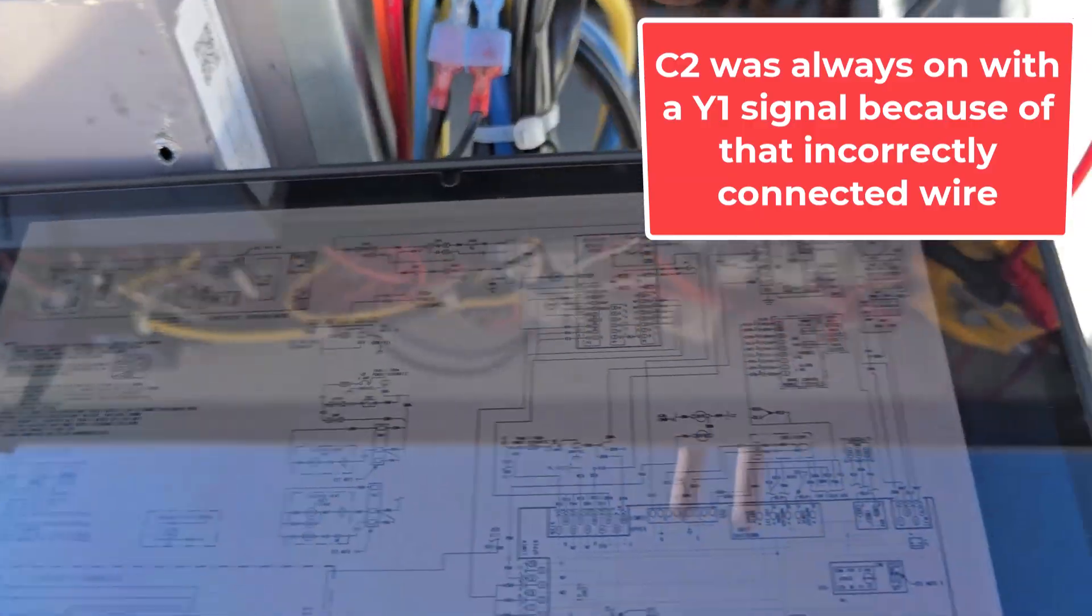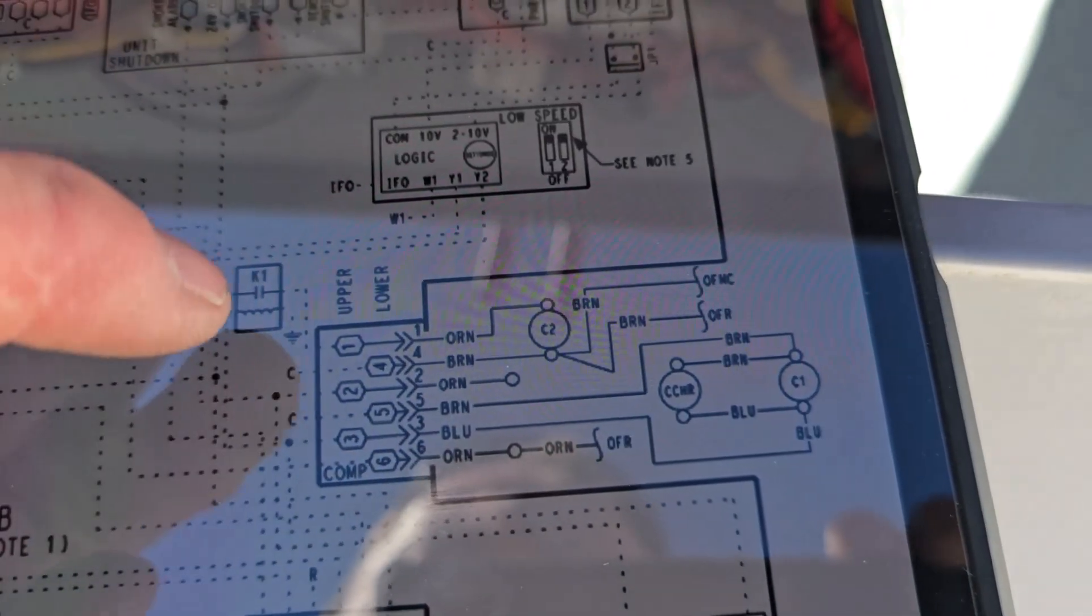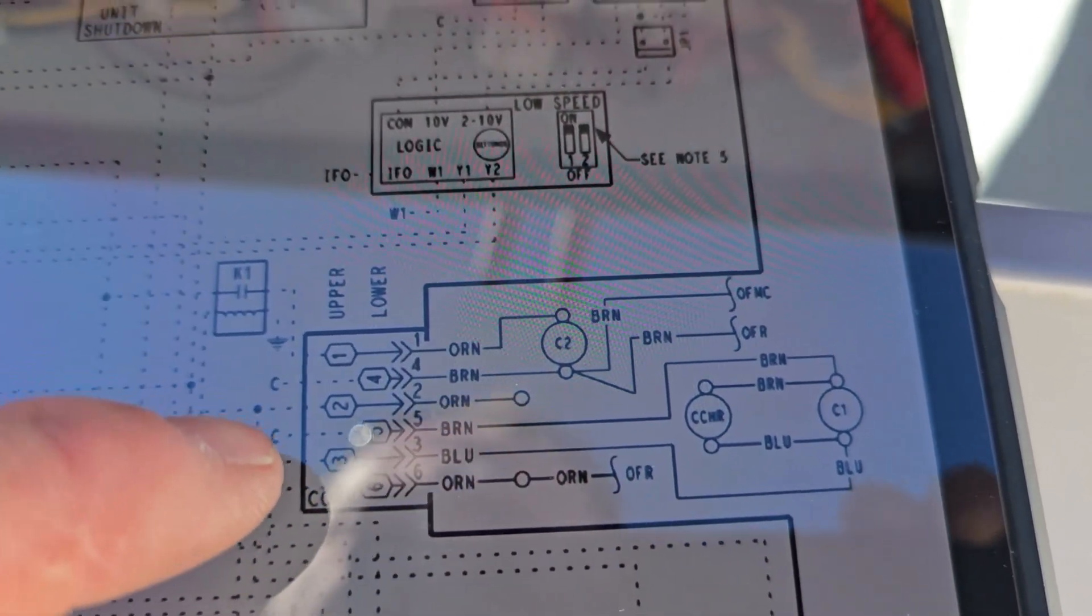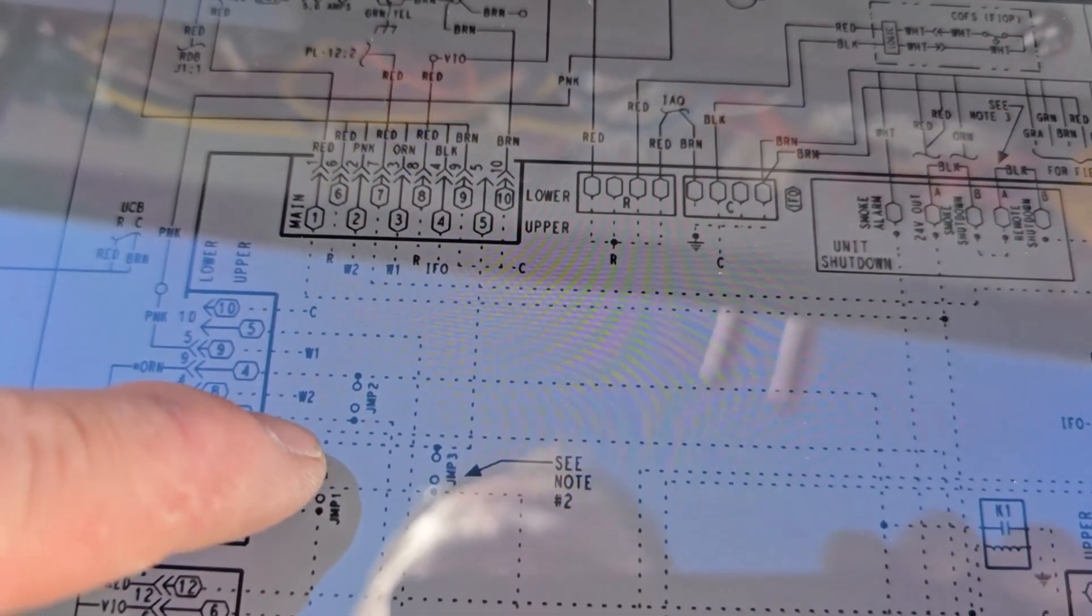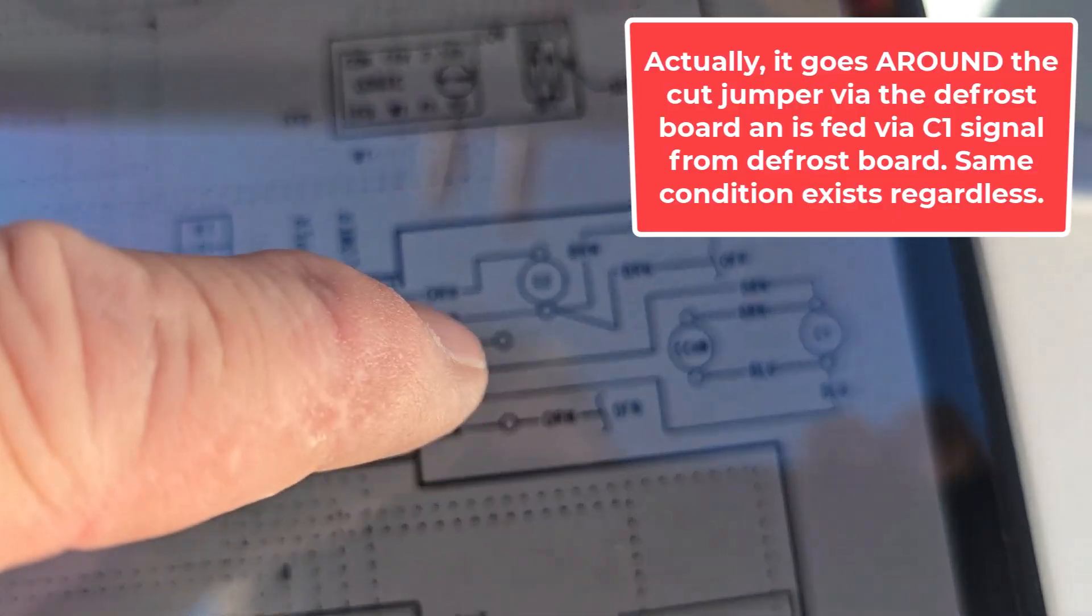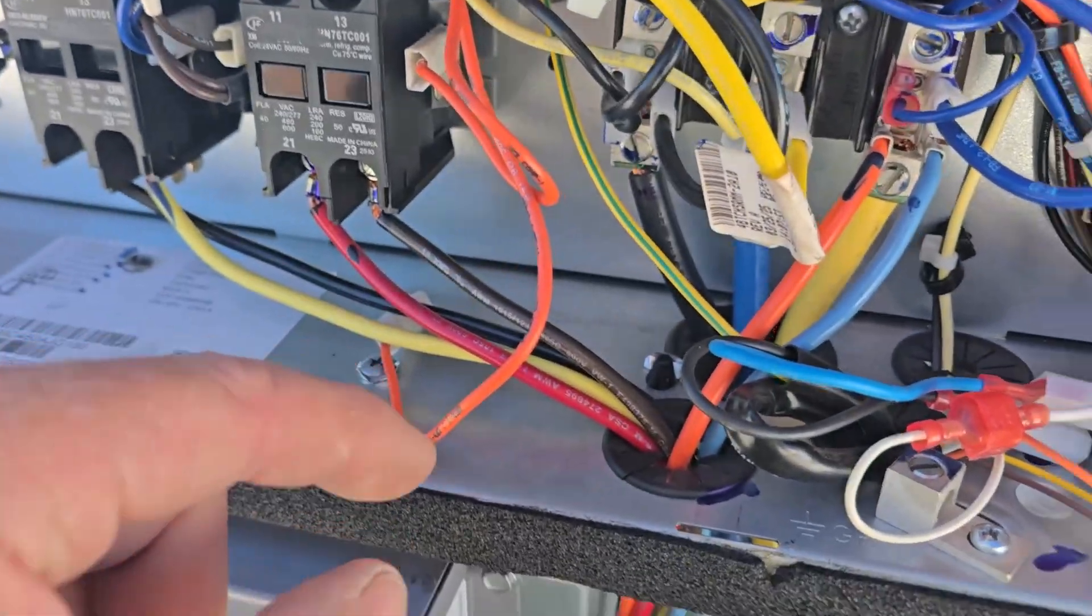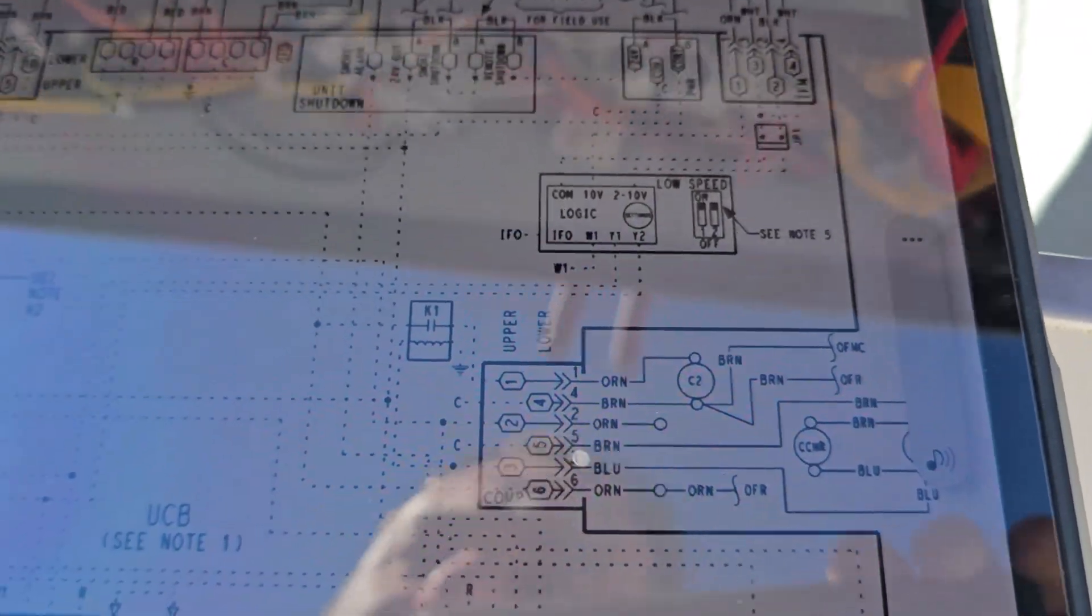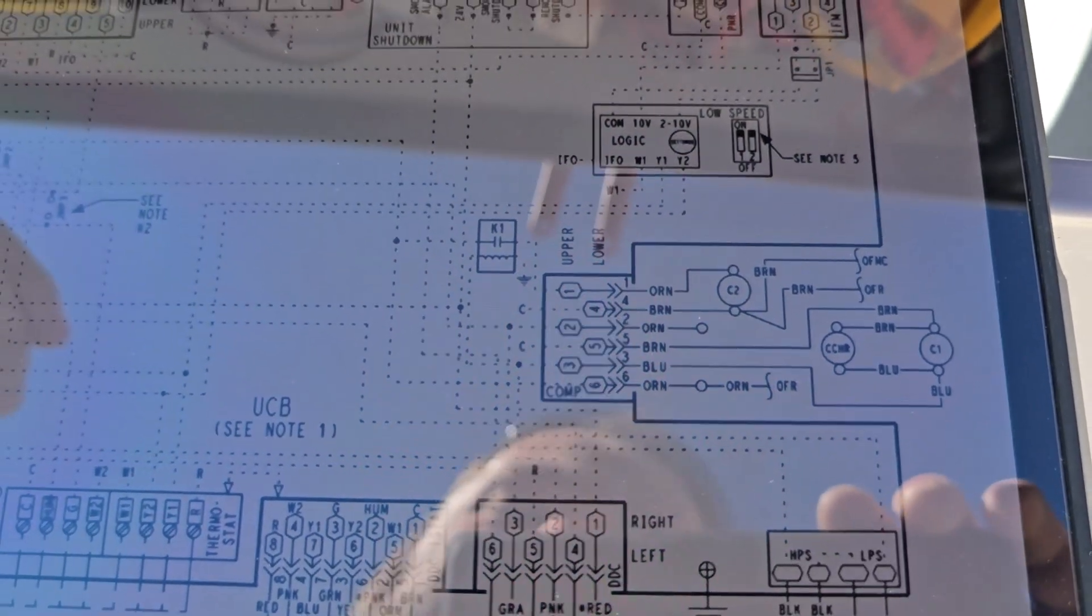So looking here on the schematic, pin 2 of comp plug, that's Y1. If you follow it, comes from Y1, Y1 goes through the jumper, comes out this trace over here, goes out this. And it's for certain models, certain options. For some reason someone at the factory tied these two oranges together. So when they did that, it was getting power to C2 compressor to contactor anytime that Y1 was active, regardless even of safety.